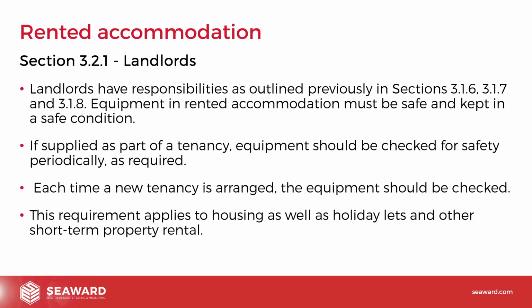Section 321, Landlords. Landlords have a responsibility as outlined previously in sections 316, 317 and 318. Equipment in rented accommodation must be safe and kept in a safe condition. If supplied as part of a tenancy, equipment should be checked for safety periodically as required. Each time a new tenancy is arranged, the equipment should be rechecked. This requirement applies to housing as well as holiday lets and other short-term rental property.